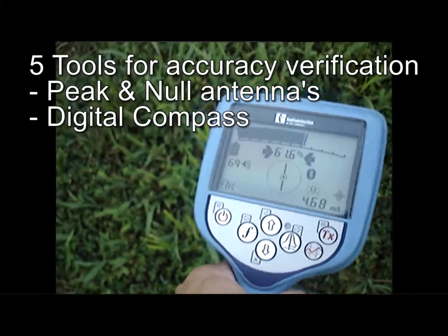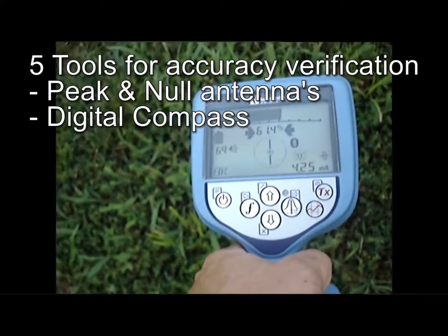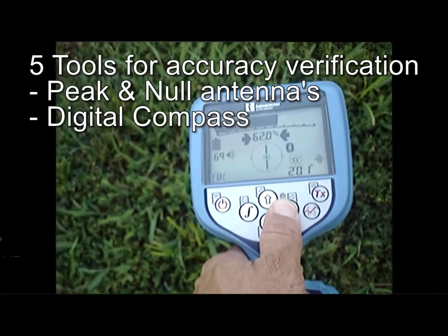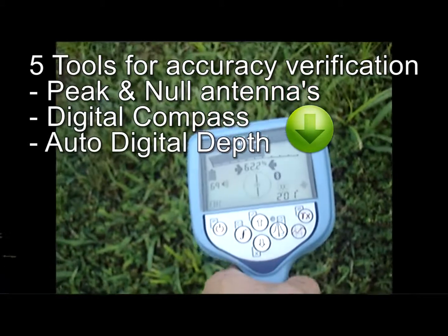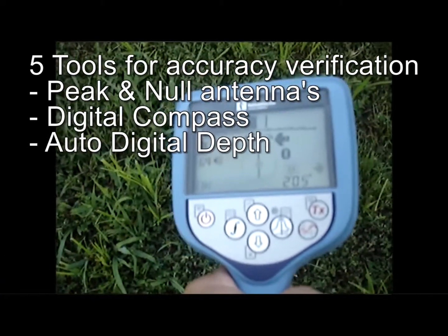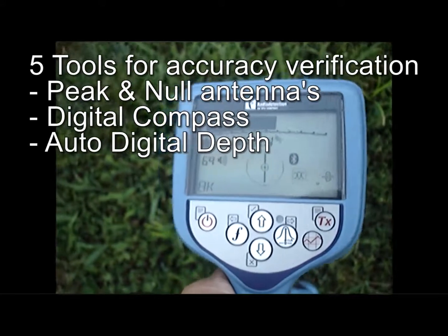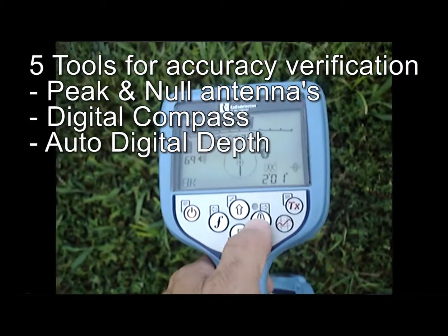As the cable or the pipe turns, the compass will turn to let you know. And we also have a constant auto depth with true depth technology. Down here in the bottom right hand corner, the depth reading will show all the time, as long as you're close to the line. You can also use that depth reading as a way to determine where the line is.